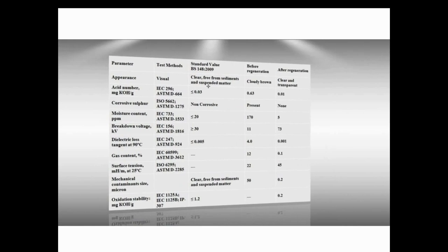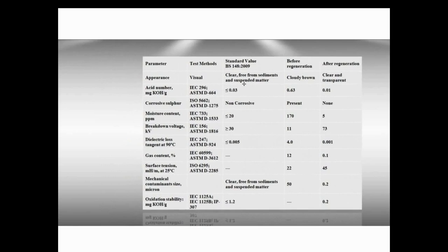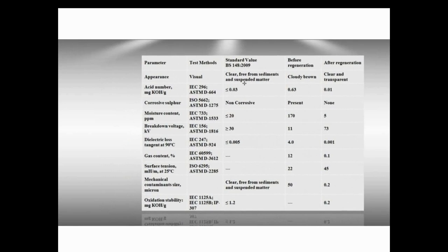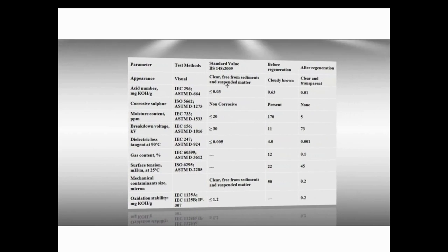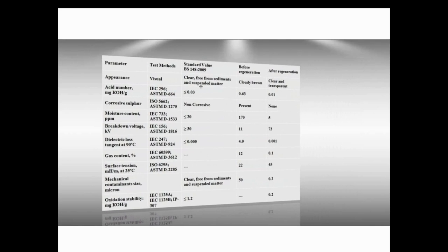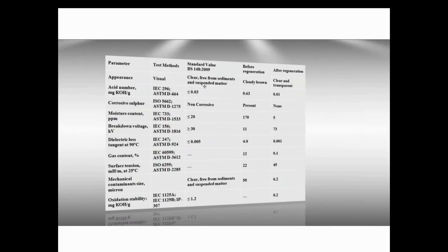There are some important regeneration results. It improves dielectric strength, it decreases tan delta or dissipation factor, it increases interfacial tension, resistivity, and oxidation stability if you add back the DBPC antioxidant inhibitor.